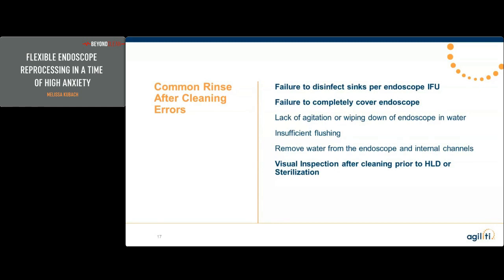But I see it all the time, especially once the schedule gets busy, the scopes are flying through, and I see no one checking the overall condition and especially the distal end under magnification. This is meant to protect the patient from maybe a sharp portion that is not visible to the naked eye, or something that might be loose, and is made to help the cleaning technician find residual debris or something that may pocket debris that would also cause an infection risk for the patient.